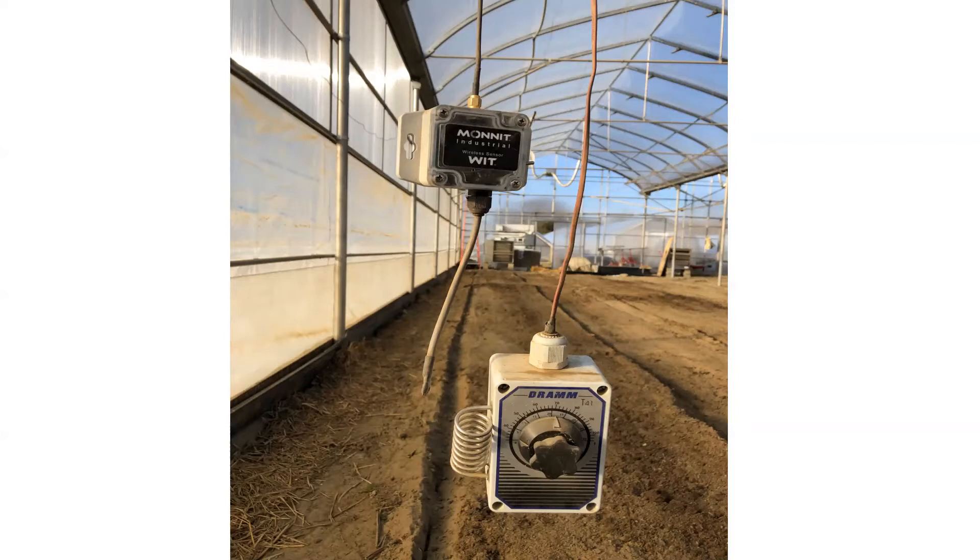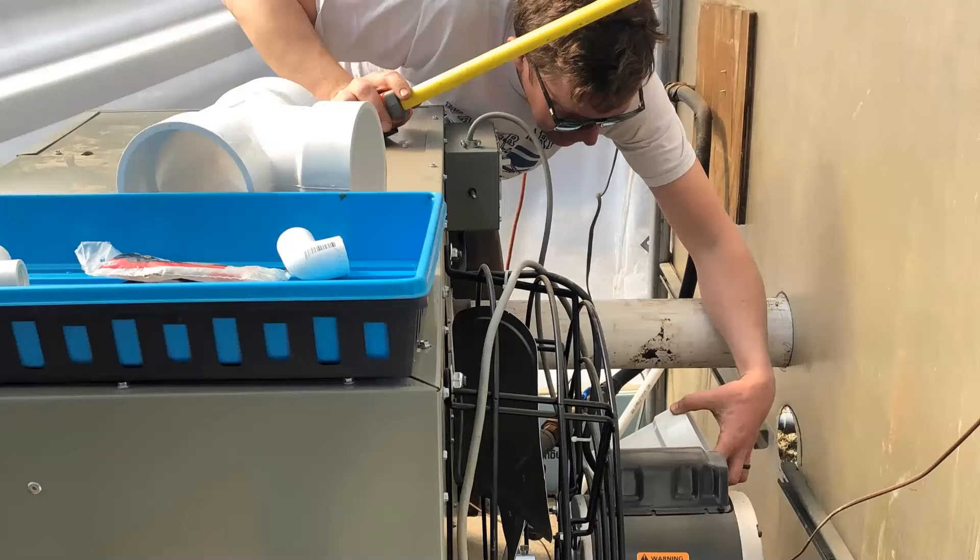We use DRAMM thermostats, accurate to plus or minus one degree. John Bartok — the guru of greenhouse energy and structural efficiency — recommended this type of thermostat and said it would pay for itself within a year. They're about $45–50, whereas the hardwired dial thermostats we were using before were only accurate to plus or minus five degrees. These keep a much more even temperature in the greenhouse. We've switched over mostly to high-efficiency heaters — 93% efficient — using PVC ductwork so they're sending most of the heat into the greenhouse rather than out a galvanized pipe.